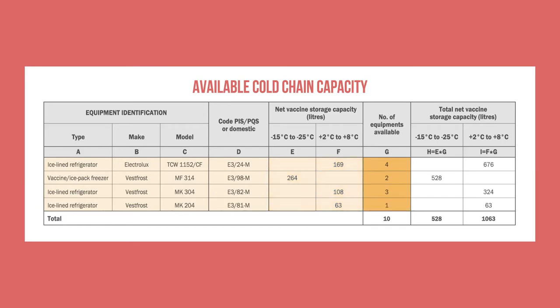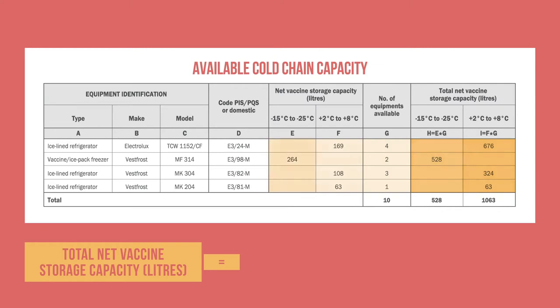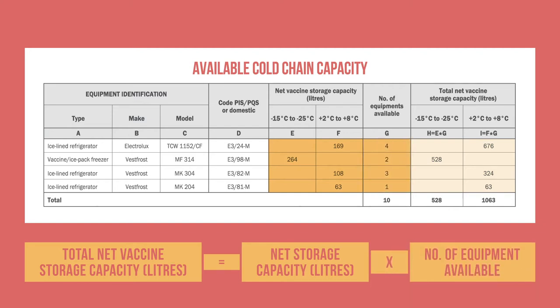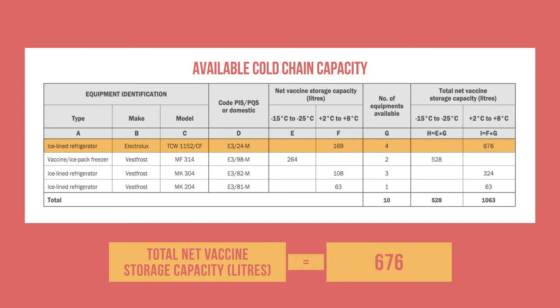Specify how many pieces of each equipment type you have available. Then, for each type of equipment, calculate the total net vaccine storage capacity by multiplying the net vaccine storage capacity of each type of equipment by the number of pieces of that equipment. For example, one type of ice-lined refrigerator holds 169 litres.